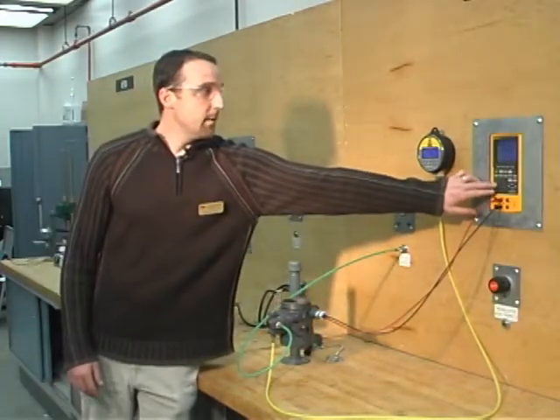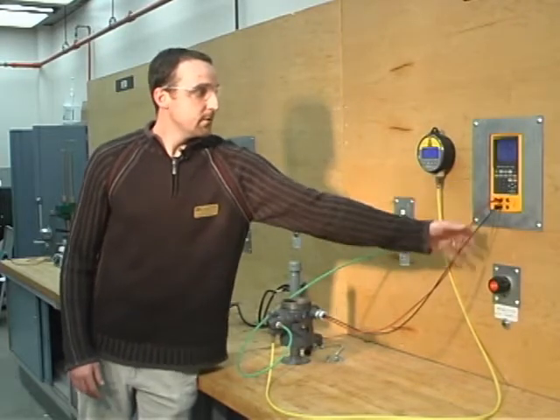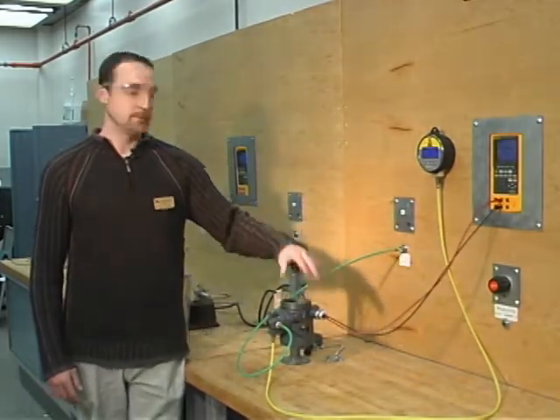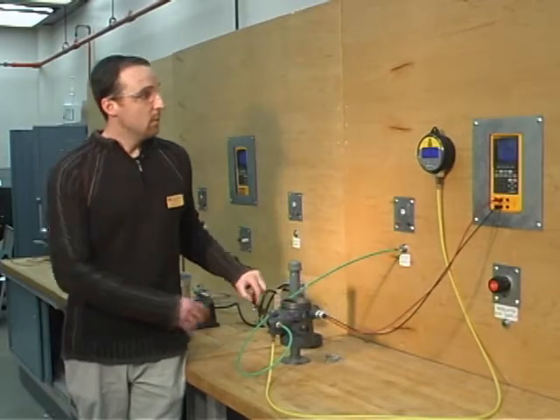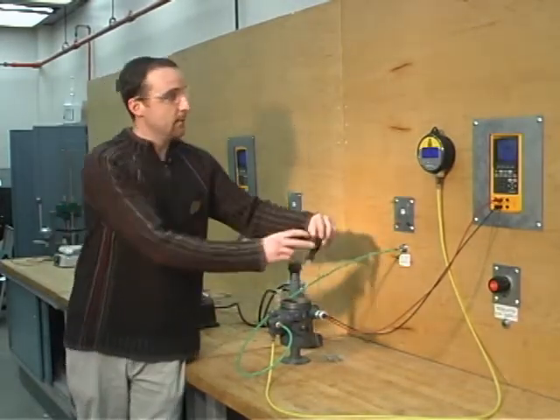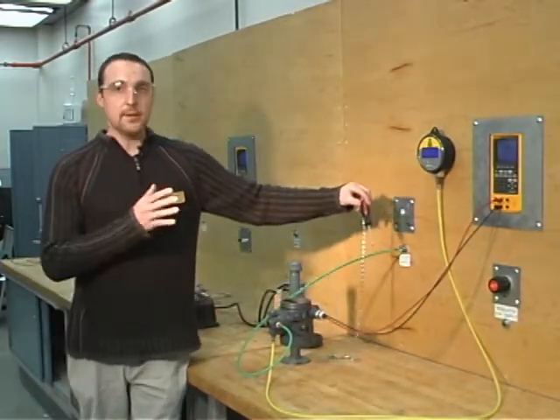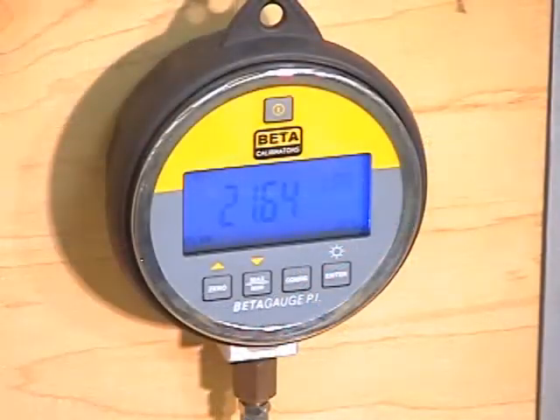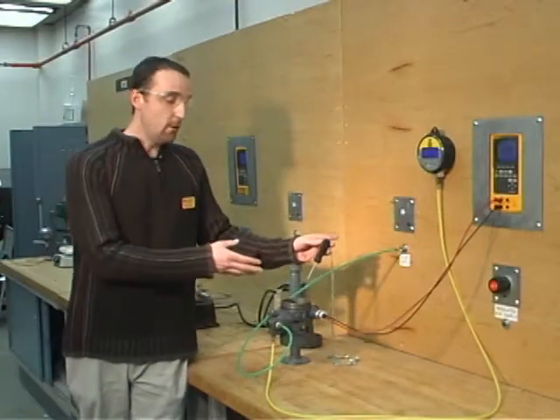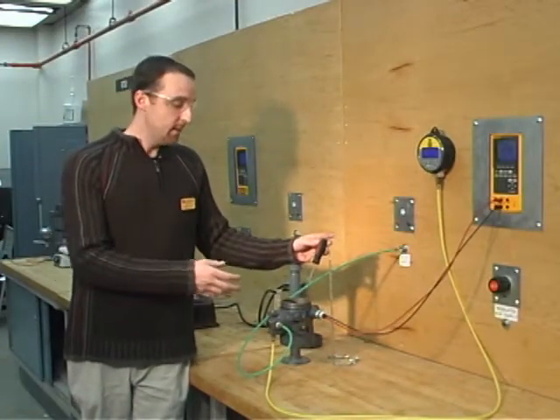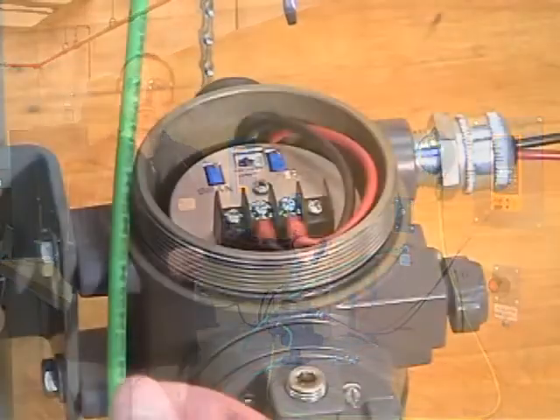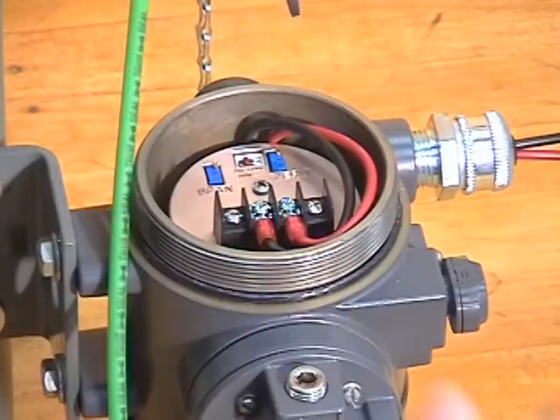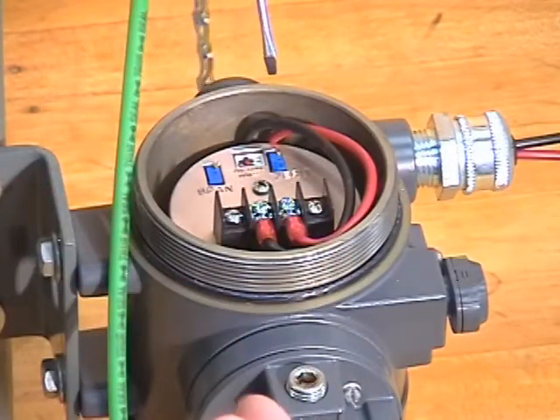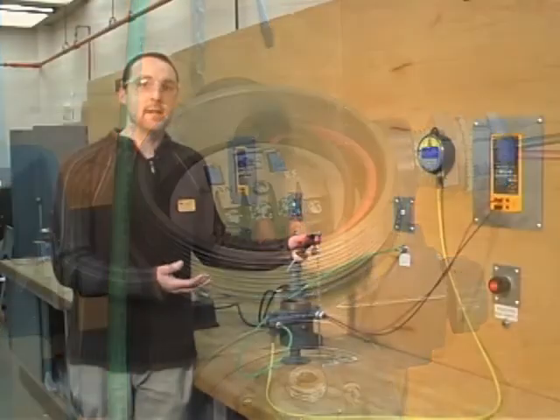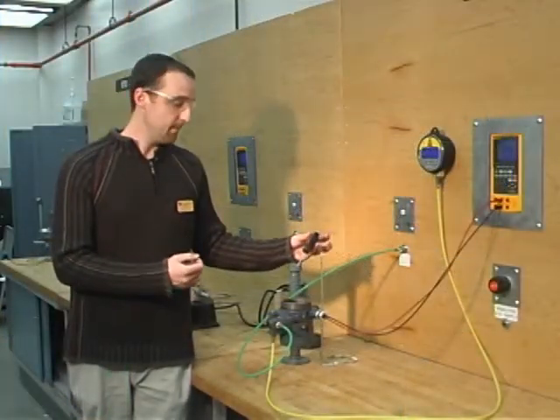We're going to start out by placing 4 milliamps through these wires to our transducer. We're looking for a 20 kilopascal output. Currently we're reading about 21.62 kilopascals, so we're going to start with adjusting our zero screw. On a transducer or a transmitter, they usually have a zero and a span screw. Our zero being 4 milliamps, 20 kilopascals, and our span being 20 milliamps, 100 kilopascals.